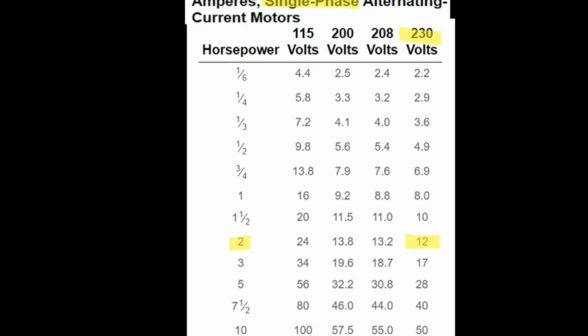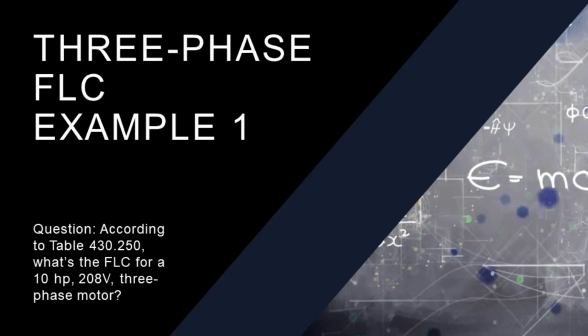All right, basically what I'm going to do is I'm getting the FLC, the code book, the full load current book answer. For a 2 horsepower motor at 230 volts, right out of the table, I'm at 12. Okay? I'm going to take that number 12. Oh, I'm ahead of myself. I'm just showing you how to use the table first, so I apologize. So that's how you get there, 12. There's more steps to this.